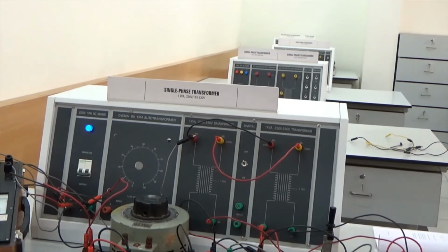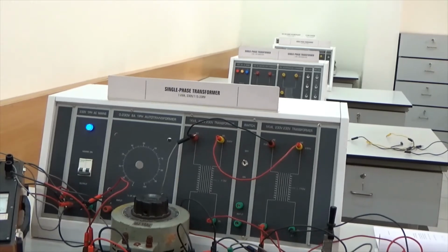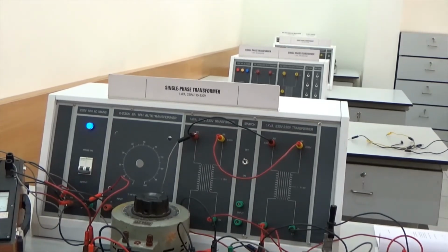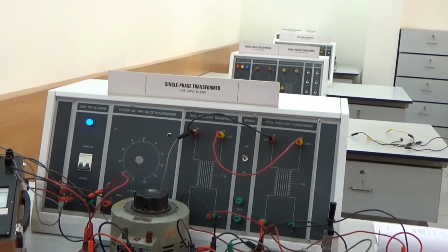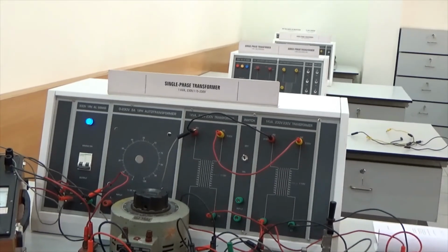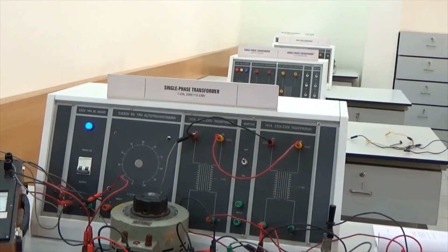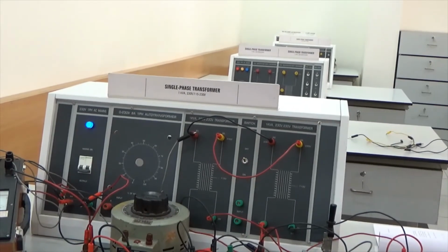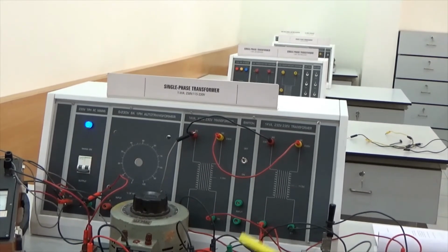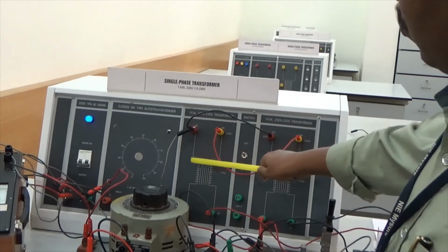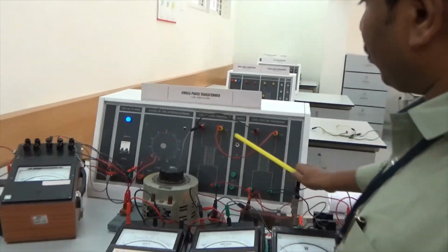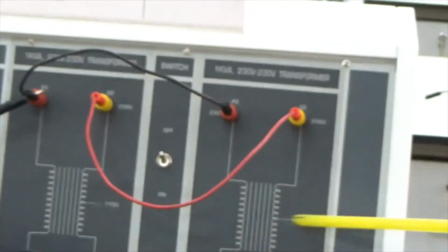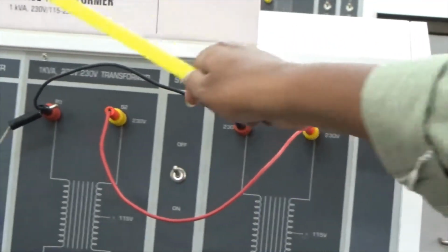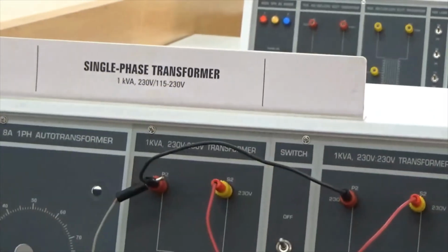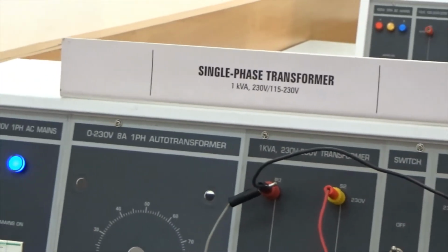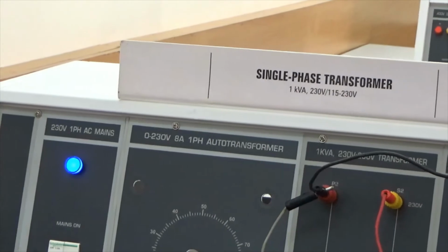So today we are going to conduct an experiment on Sumpner's test. It is a back-to-back test on the transformer. In this experiment, the objective is to find out the predetermination of efficiency of both the transformers. We are using two identical transformers in this case, 1:1 transformers, 1 kVA, 2 sets, and the voltage rating is 230 volts for both the transformers, and both are connected as per the circuit diagram.